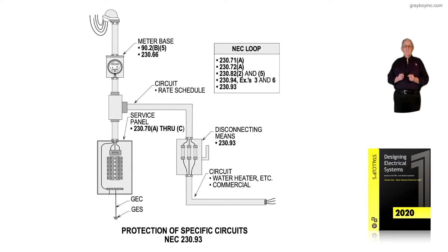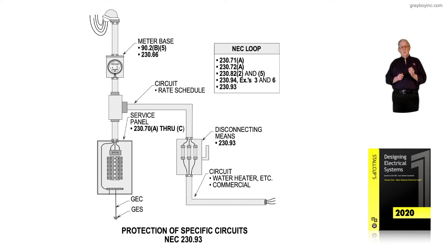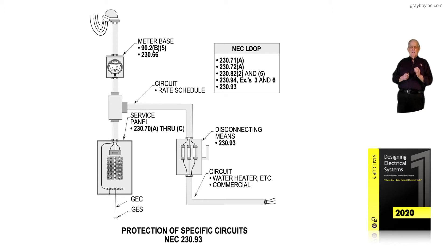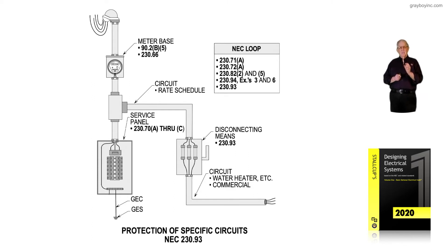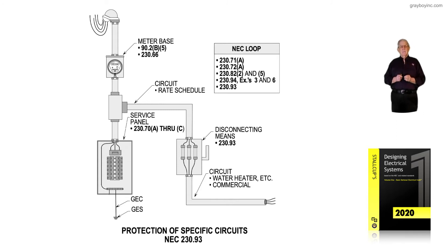This illustration deals with protection of specific circuits in accordance with 230.93. Reviewing that illustration, we're making a tap ahead of the main in the service equipment to the left. By NEC requirements, we would have to review 230.82 and see if one of those permissive taps ahead of the main could be made to supply the disconnecting means tapped ahead of the main, as seen in the illustration.